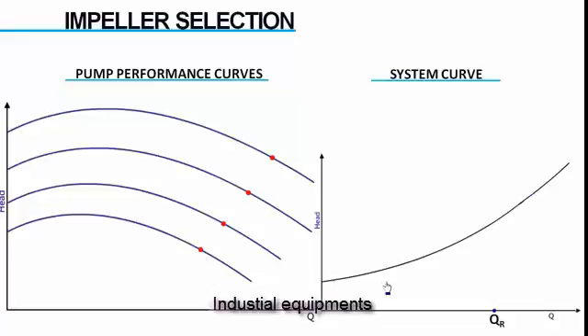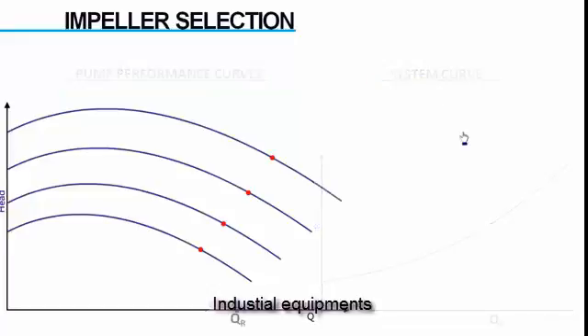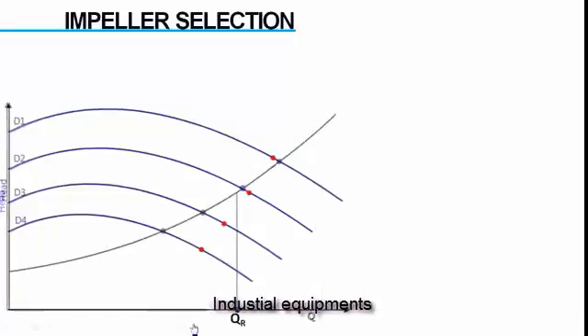The operating point of pump will be intersection point of system curve and pump performance curve. So, depending upon selection of impeller, the pump could operate anywhere here. But we have requirement of specified flow rate. Out of these operating points, this is the one which is most near to the required flow rate. So we will select this impeller.